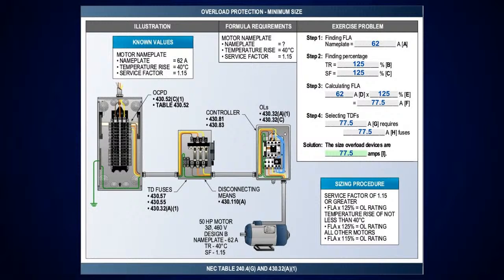Right. Now, we talked about this last week, and when you go over and you look at 430.32, it tells you, well, you have a motor with a service factor 1.15 or greater, and a temperature rise that's 40 degrees C or less. Okay? You'll take those at 125%. If you don't meet both of those, then you have to take it at 115%. Okay? So my nameplate value is 62. I met the temperature rise and service factor, take it at 125%, and that's going to tell me that my overload devices there will be rated at 77.5 amps.